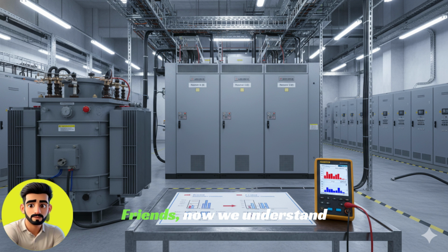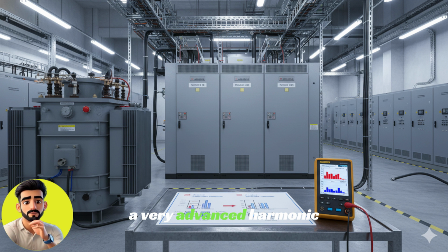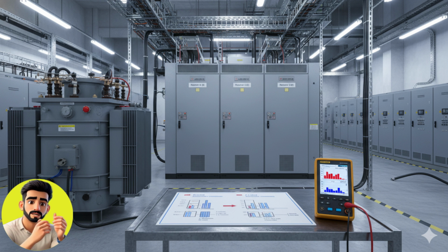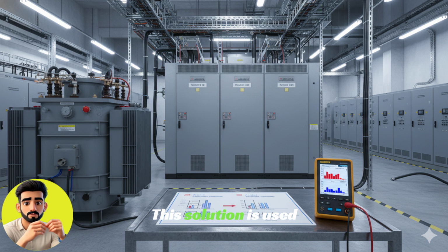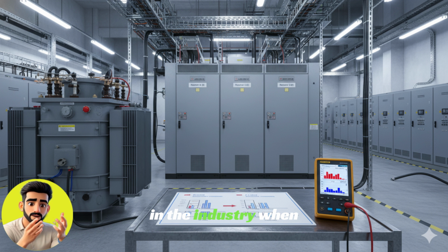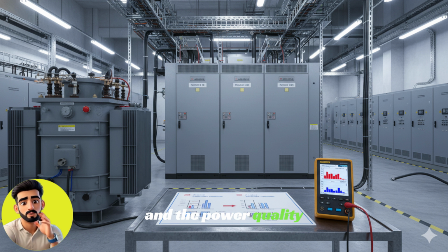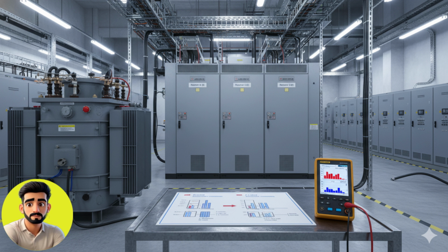Friends, now we understand a very advanced harmonic solution. Its name is multi-pulse drive. This solution is used in the industry when the load is heavy, the transformer is critical, and the power quality standards are very strict. Let's understand in simple language how the multi-pulse drive reduces harmonics.